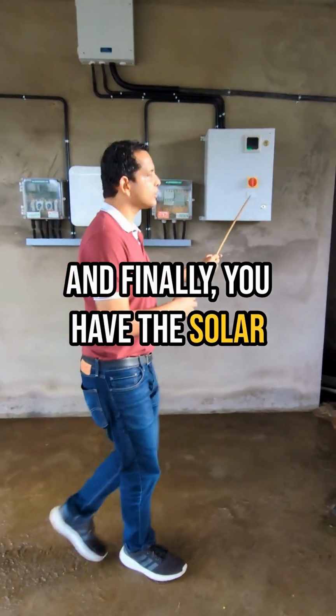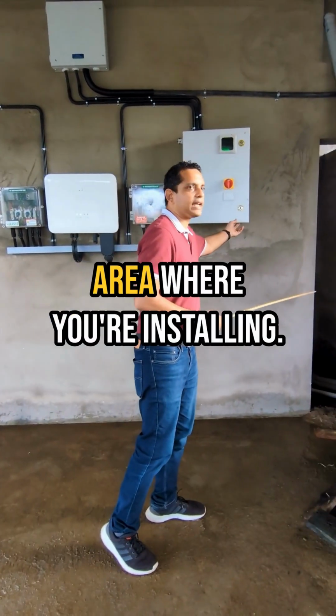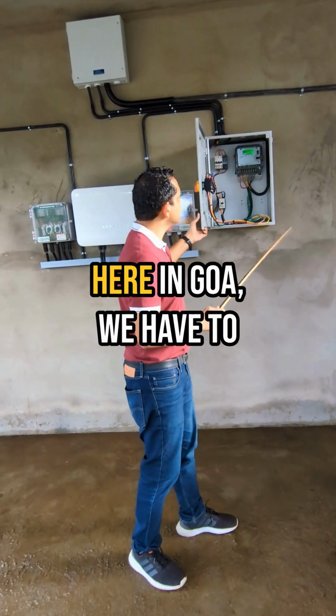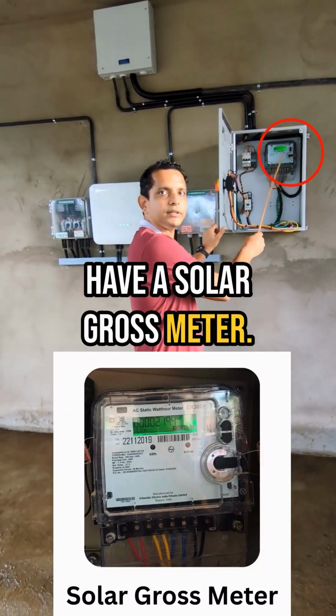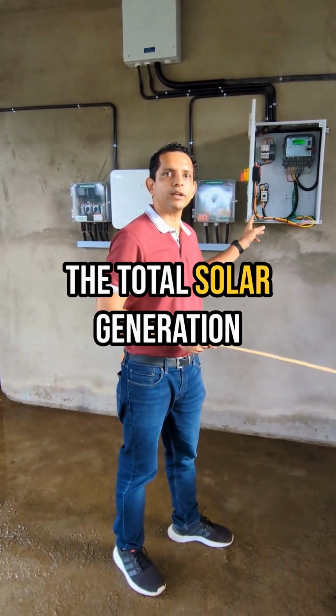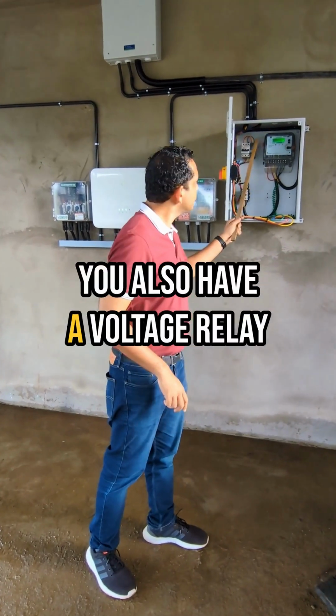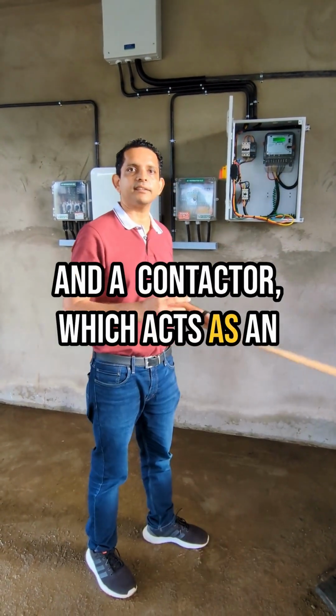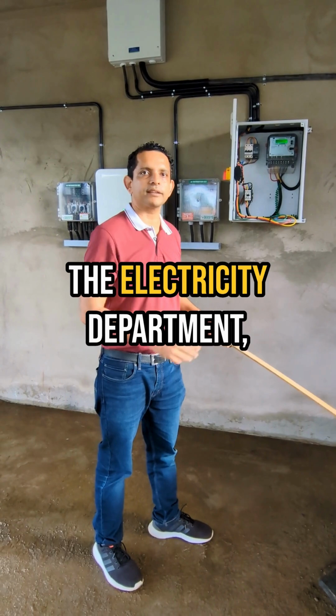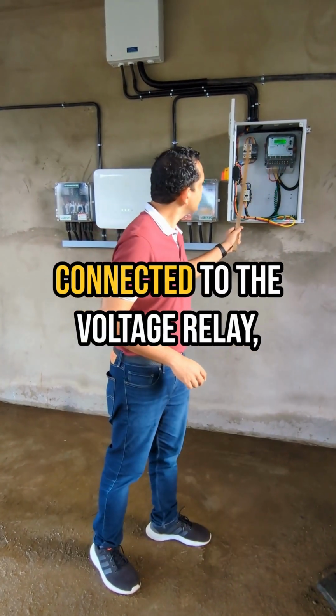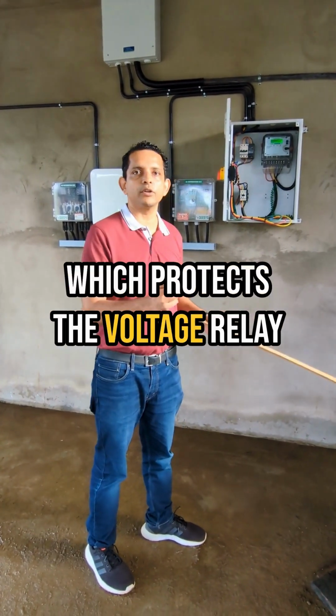Finally, you have the solar gross meter. This is specific to the area where you're installing. Here in Goa, we have to have a solar gross meter. This gross meter will give you the total solar generation from the plant. You also have a voltage relay and a contactor, which acts as an additional layer of protection to the electricity department. And you have an MCB that is connected to the voltage relay, which protects the voltage relay from any surges.